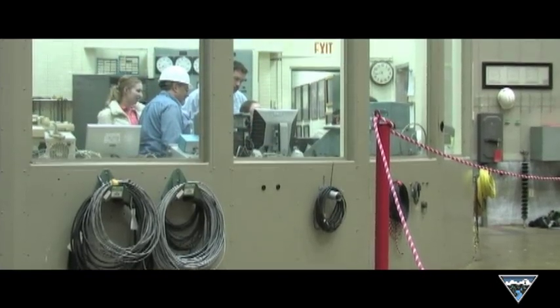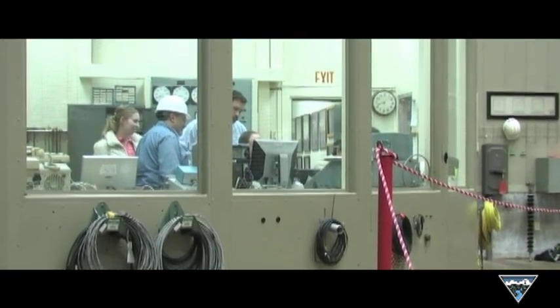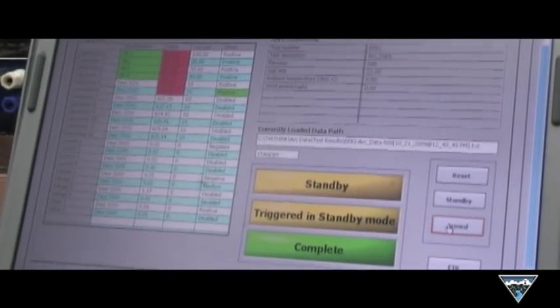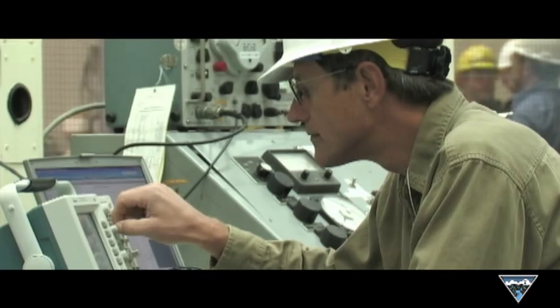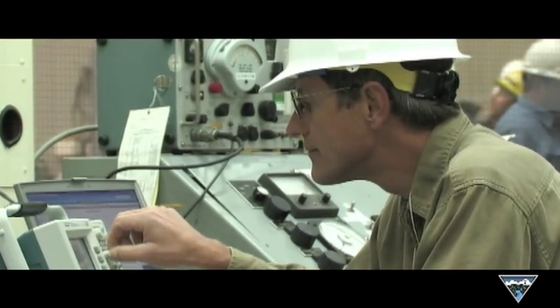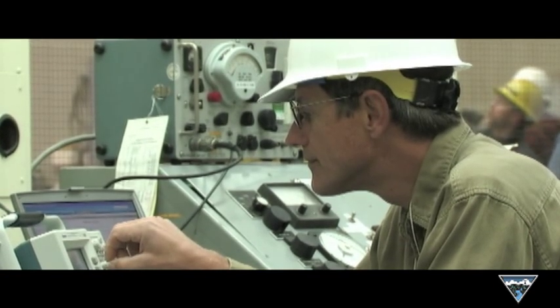The arcs that we're producing here today are not likely to burn someone. But what they can do is validate the models that are used to calculate the exposure of the workers at higher arc currents. Unfortunately, to actually reproduce the burning conditions, we would have to cause a system disturbance. And our customers don't like that for some reason.